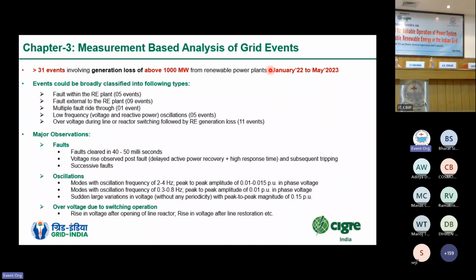So, the major insights from the measurement-based analysis: 31 events, as I already mentioned, have taken place between January 22 and May 23. What was common between these events? We have tried to classify them into 5 categories. In some cases, the initiating event was a fault within the RE plant. In some cases, the initiating cause was a fault external to the RE plant. In some cases, the generation loss was because of multiple faults within a short duration of time. Some of the plants were able to successfully ride through the first fault, but were not able to do the same in case of the second fault that took place a short time after the first one.